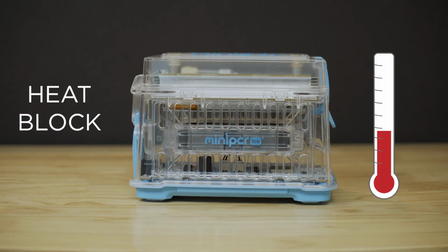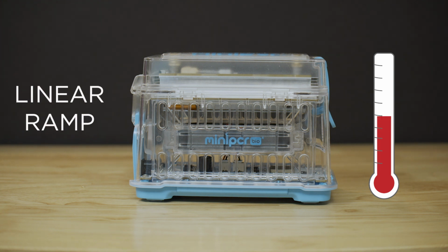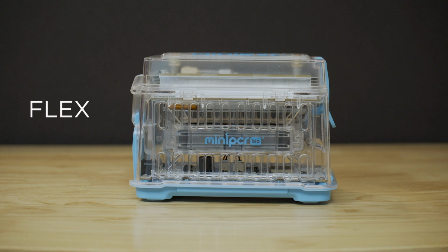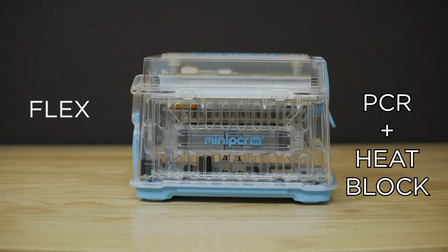The heat block option programs the machine to hold one temperature for a set period of time, while linear ramp programs the machine to start at one temperature and slowly ramp to a different temperature over a set period of time. Flex allows you to link different program types together in series, like a PCR followed by a heat block or vice versa. These programs can additionally include touchdown PCR.